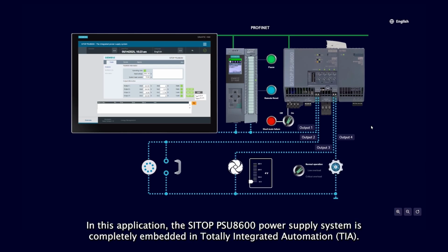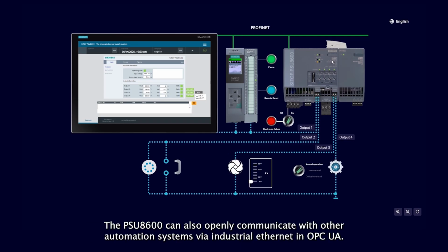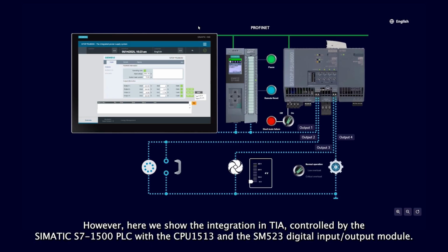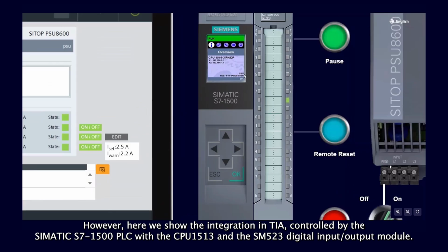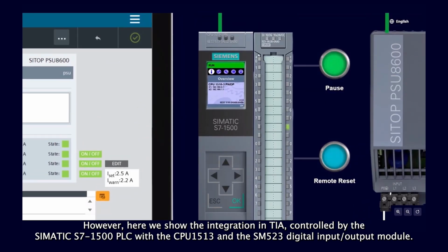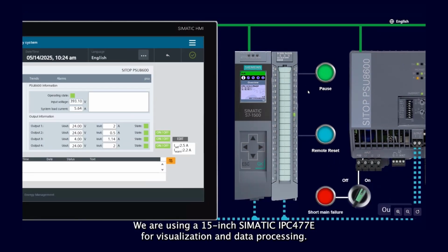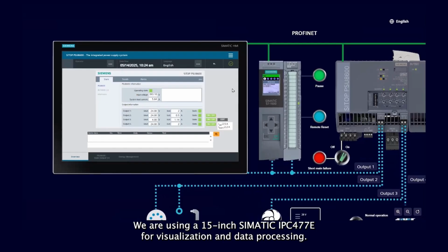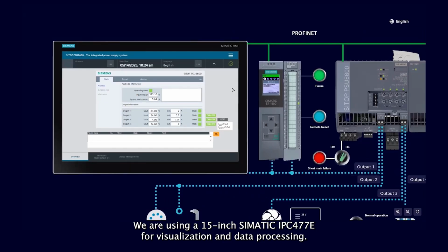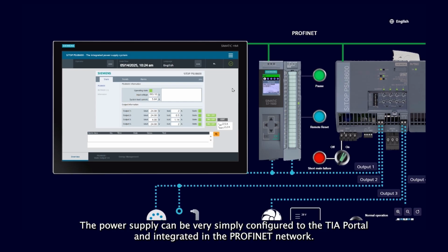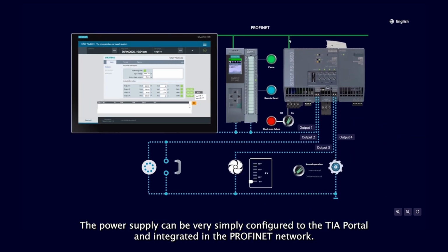In this application, the SITOP PSU8600 power supply system is completely embedded in totally integrated automation. The PSU8600 can also openly communicate with other automation systems via Industrial Ethernet in OPC UA. However, here we show the integration in TIA, controlled by the SIMATIC S7-1500 PLC with the CPU 1513 and the SM523 digital input-output module. We are using a 15-inch SIMATIC IPC477E for visualization and data processing. The power supply can be very simply configured through the TIA portal and integrated in the Profinet network.